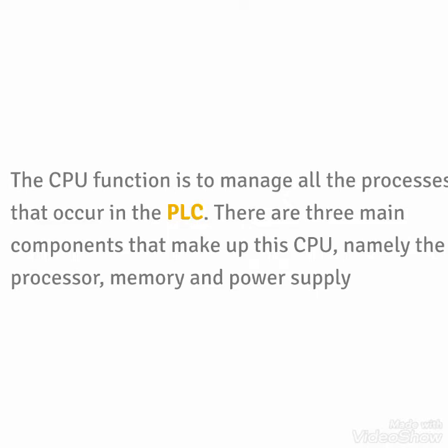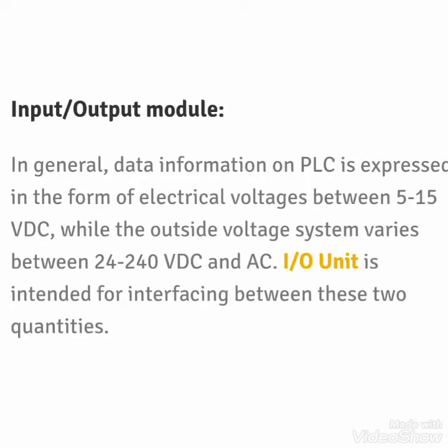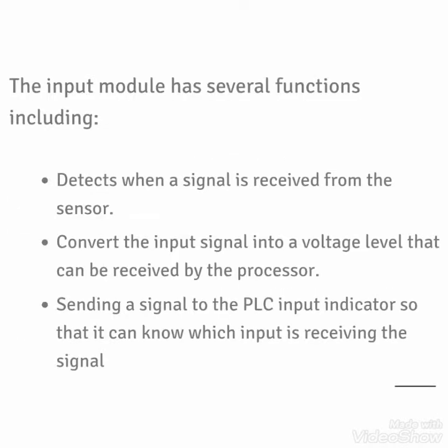For input/output modules, data information on the PLC is expressed in the form of electrical voltage between 5 to 15 volt DC, while the outside voltage system varies between 24 to 240 volt DC and AC. The input/output unit is intended for interfacing between these two quantities.